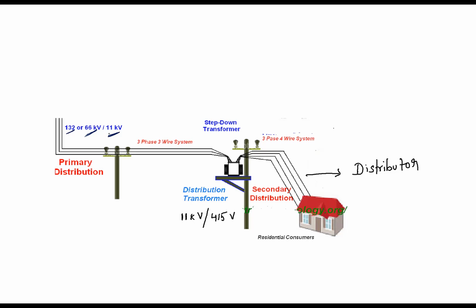Distribution is carried out in a three-phase, three-wire system. The fourth wire, called neutral, comes into picture only after the distribution transformer, when we want to distribute power to single-phase customers. Until that point, the power system has only three phases and three wires. Even in your distribution transformer, the primary voltage is 11 kV, and the 11 kV line only has three conductors - R phase, Y phase, and B phase. There is no neutral on the 11 kV side.